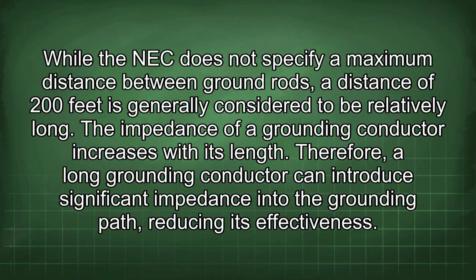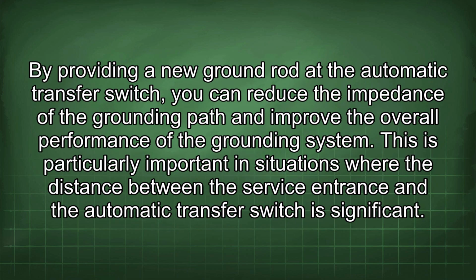While the NEC does not specify a maximum distance between ground rods, a distance of 200 feet is generally considered to be relatively long. The impedance of a grounding conductor increases with its length. Therefore, a long grounding conductor can introduce significant impedance into the grounding path, reducing its effectiveness. By providing a new ground rod at the automatic transfer switch, you can reduce the impedance of the grounding path and improve the overall performance of the grounding system.